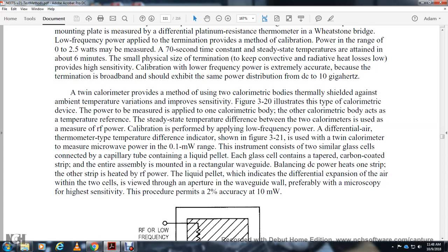A twin calorimeter provides a method of improving sensitivity. The twin calorimeter is thermally shielded against ambient temperature variation. Figure 3.20 illustrates this type of calorimeter device. The power being measured is applied to one calorimetric body. The other calorimetric body acts as the temperature reference, and the temperature difference between the two calorimeters is measured. Radio frequency power calibration is performed by applying low frequency power, with a differential air thermometer as the temperature difference indicator shown in figure 3.21.